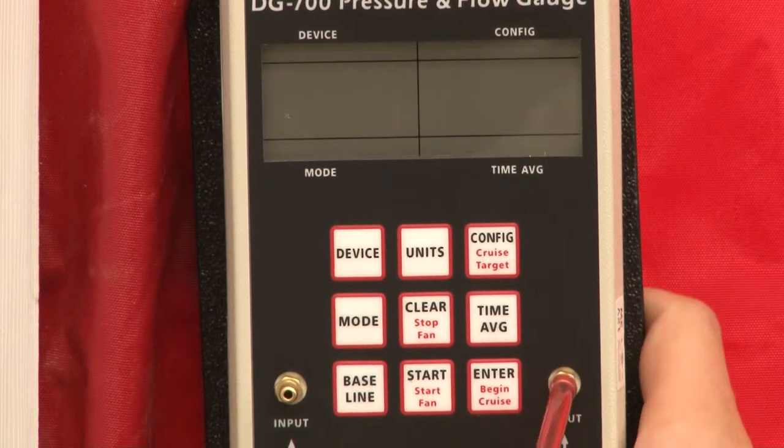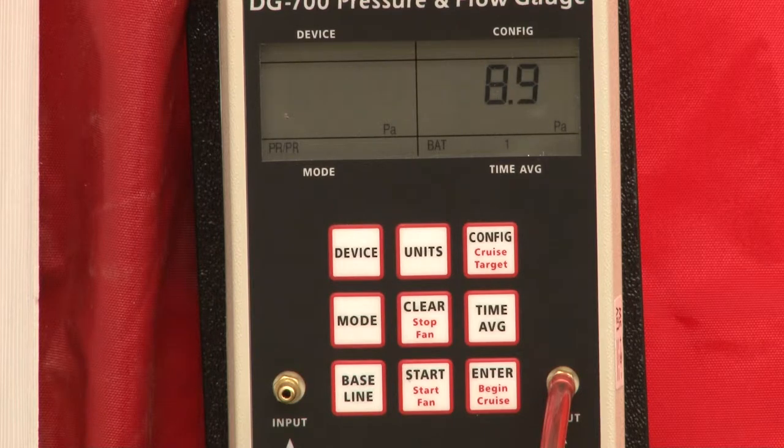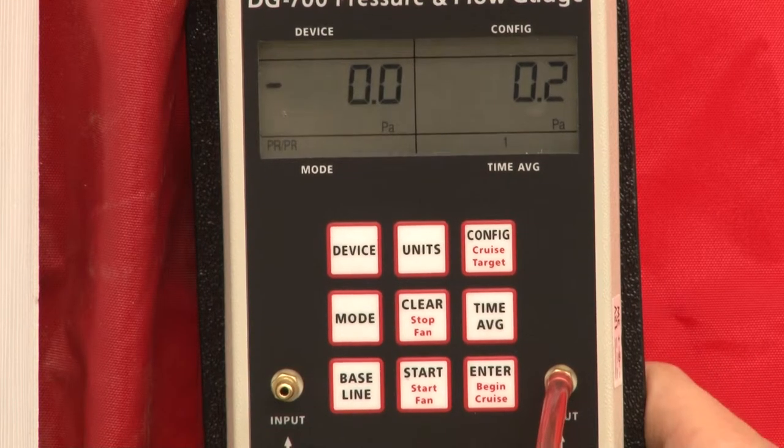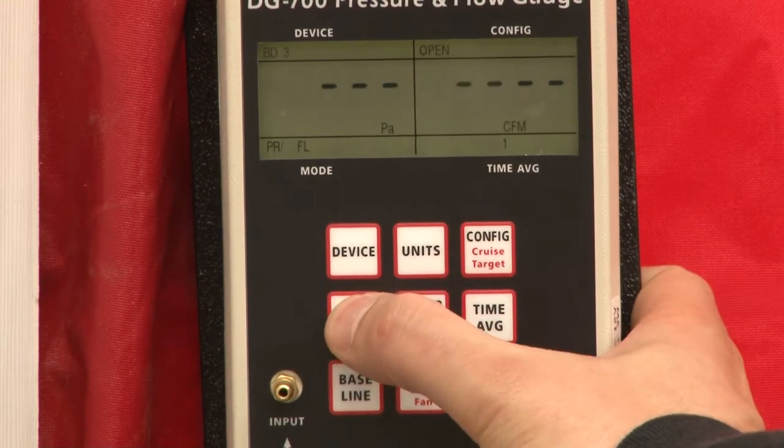Getting ready to turn our manometer on. The first button push is going to be obviously the on button. If you want to turn on your light so you can see it, you can do that. That's fine. Okay, now there's five main button pushes to get the DG700 set up to perform the blower door test.